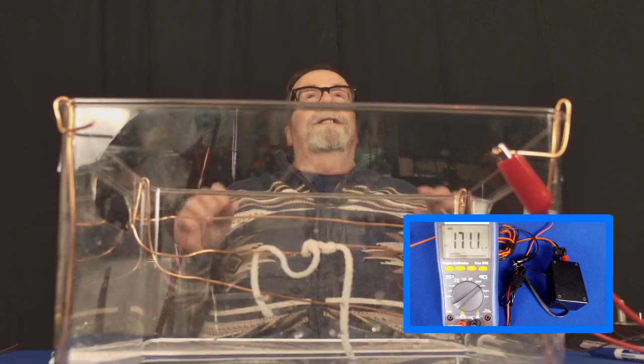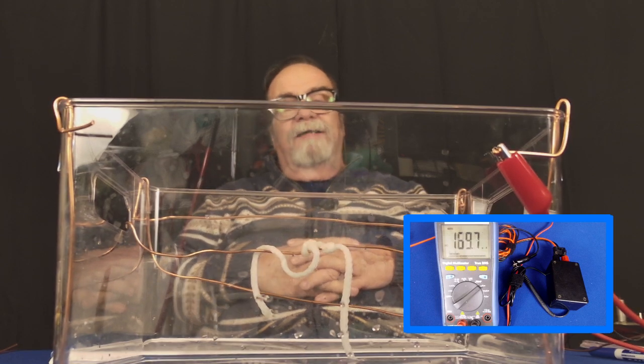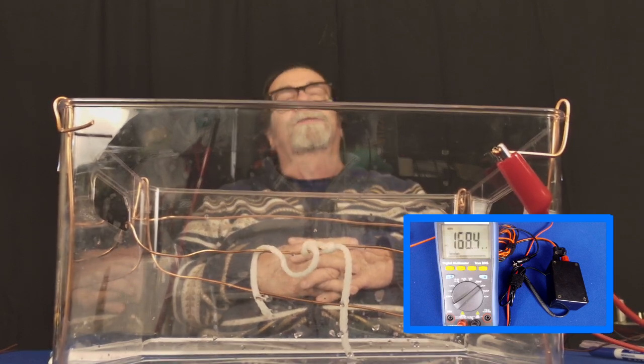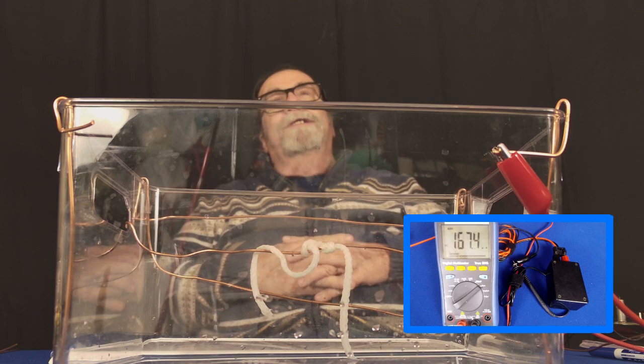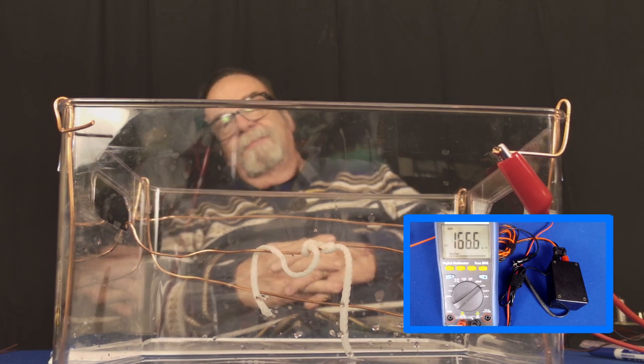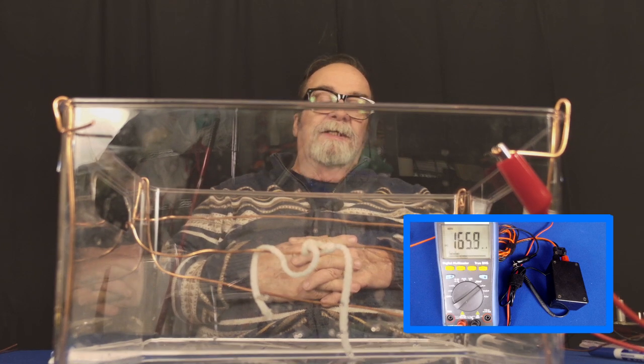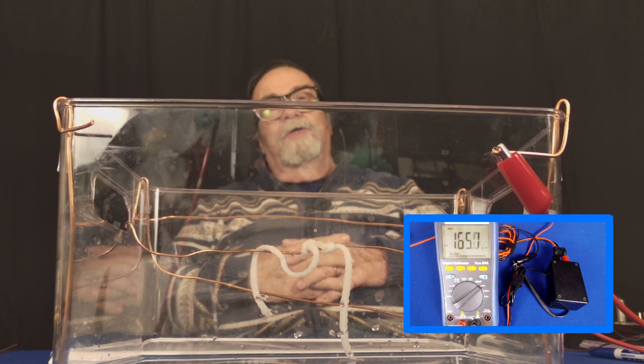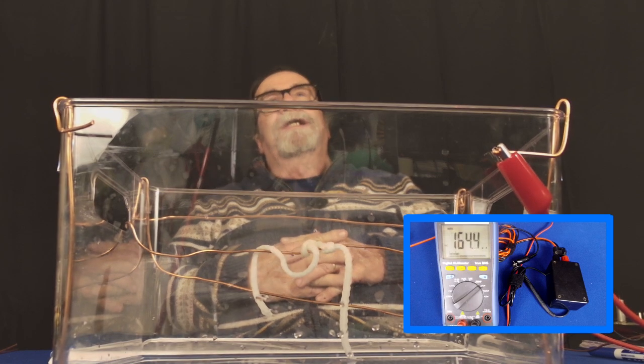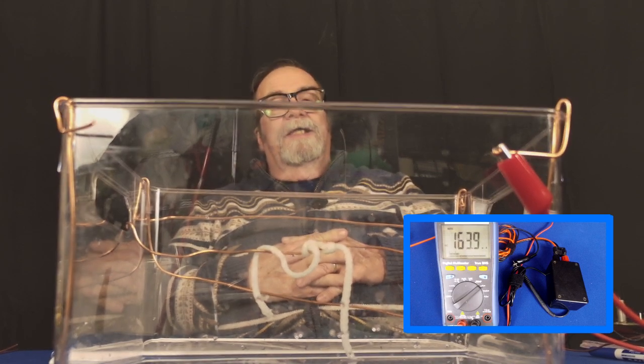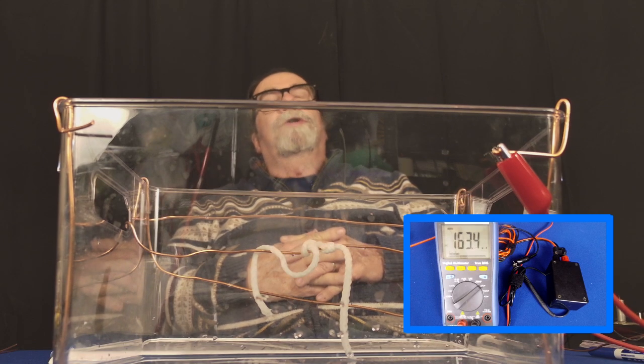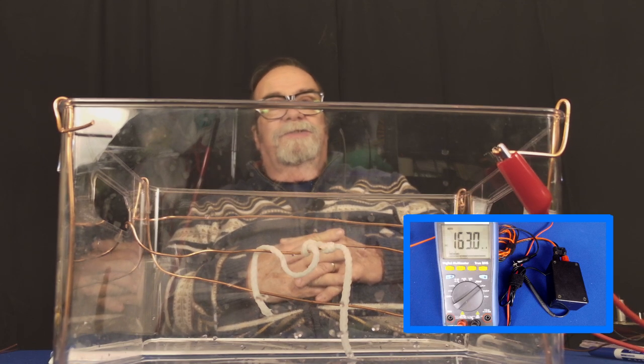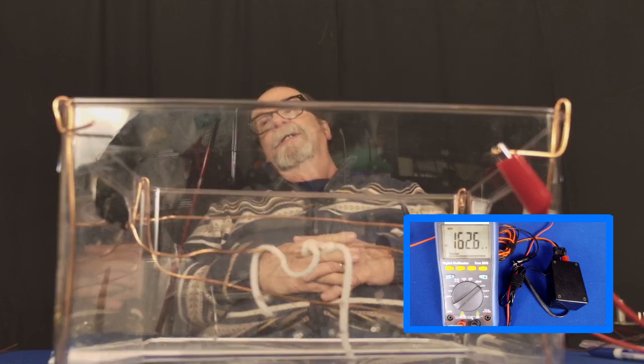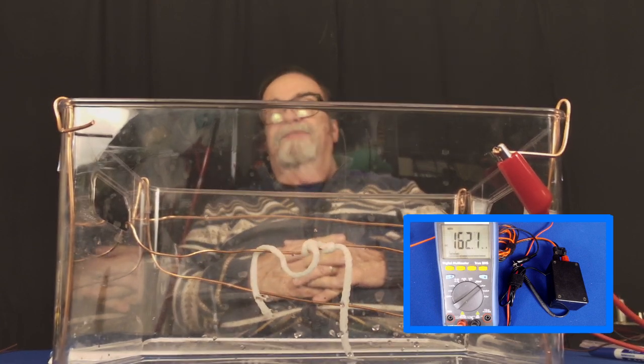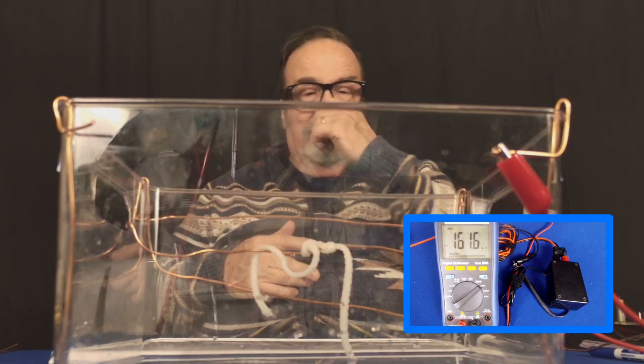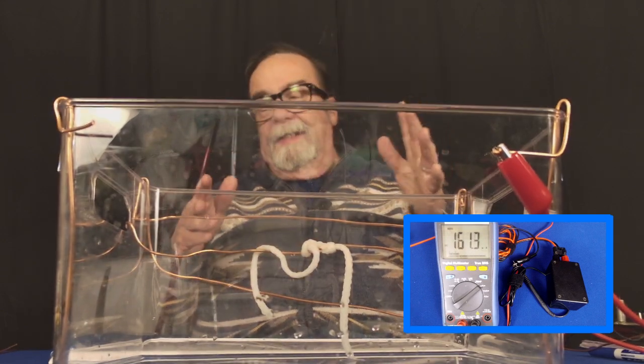And believe me, it doesn't necessarily have to be a damaged wire, because I have pulled fire cable out of conduit that has literally been pink. Remember, many of the systems out there have been out there for years. Panels may change, wiring does not. And if that wiring stays in that water-filled conduit long enough, and it's a fire cable, it will actually leach pink. And when you pull the wire out, the water will have actually seeped through the insulation and inside of that jacket. So yes, you can have bad cabling in conduit that'll cause this problem. So this is a good way to find that.